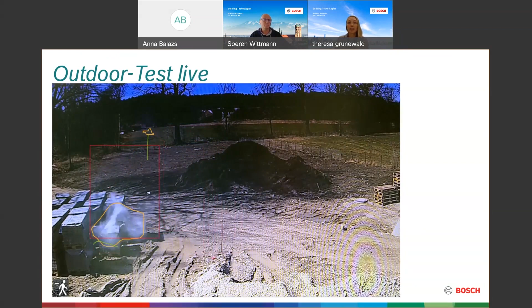And what we can see here is that the smoke is much more turbulent. But still, AVIOTEC detects it. And this is what needed to be developed. And true, in the outdoor area, there can be much more wind, for example, but based on dedicated planning, so how we plan the AVIOTEC to be installed in an outdoor area, which opening angles to be used, and also which settings we can make, this enables the AVIOTEC to perform really great also under weather conditions.